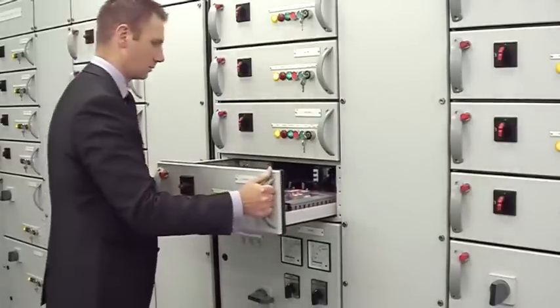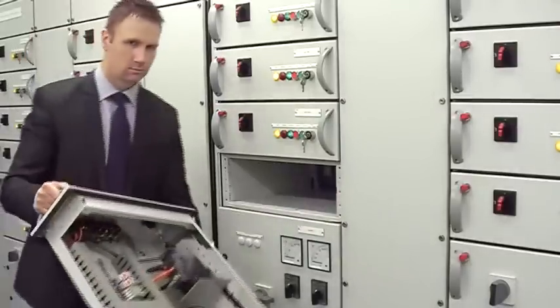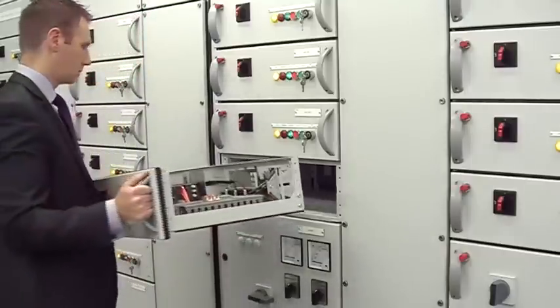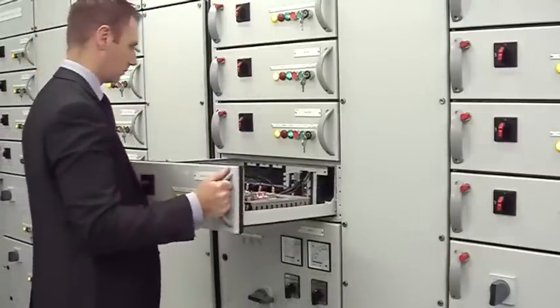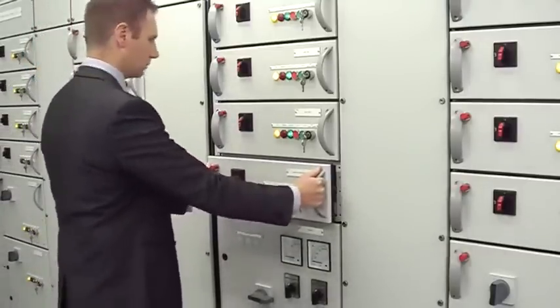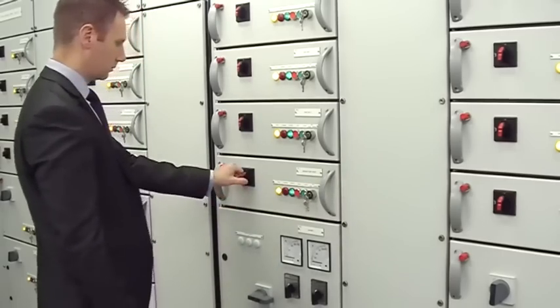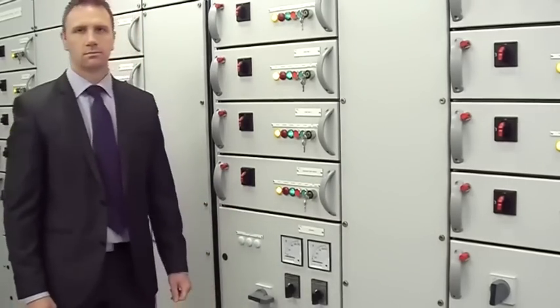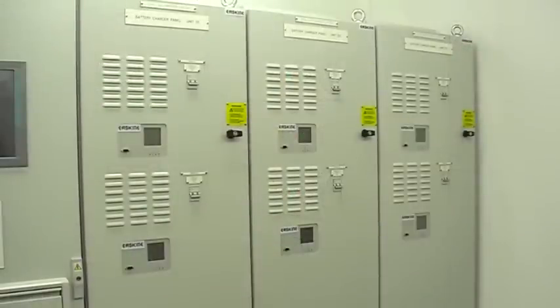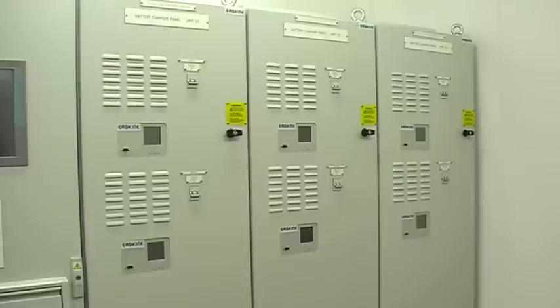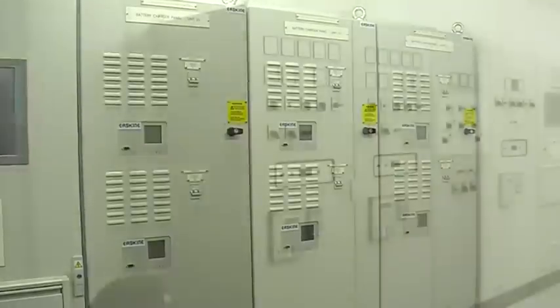The motor control centre is constructed in a Form 4 configuration and fully withdrawable to minimise downtime during component failure and to allow quick replacement of an entire starter assembly if required. Dual redundant battery chargers are used to convert the AC supplies to DC, which is used to power the turbine control systems and charge the batteries.